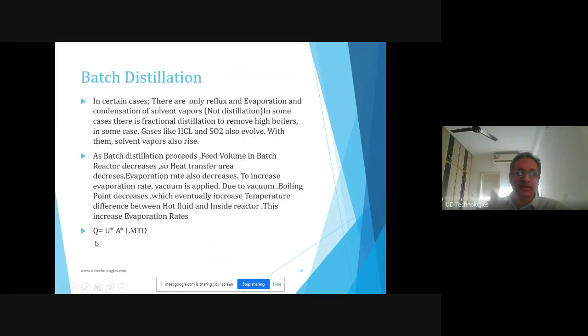So simply your Q will be increasing, so the evaporation rate also increases. You know the equation, that is Q equals U times LMTD equals M lambda. Lambda is the latent heat of vaporization of the solvent and M is the mass flow rate. So when you increase the temperature difference, it is directly proportional to the evaporation rate.